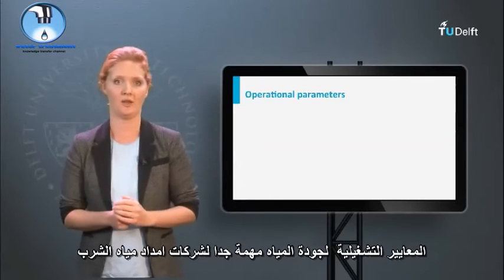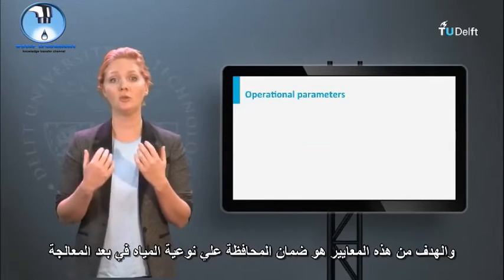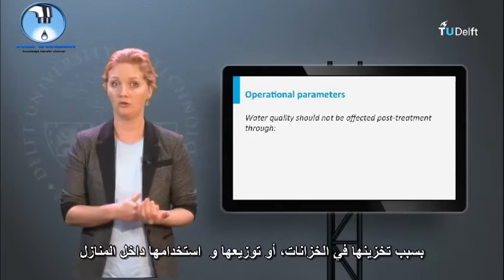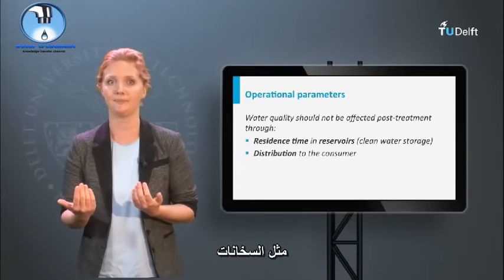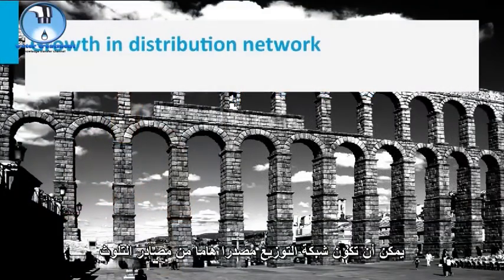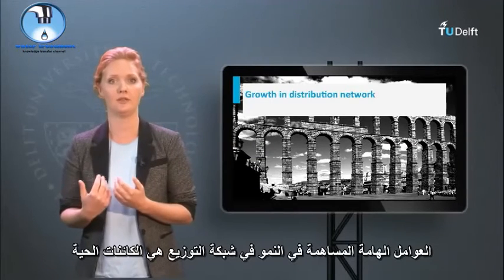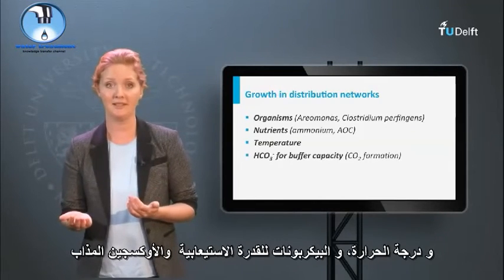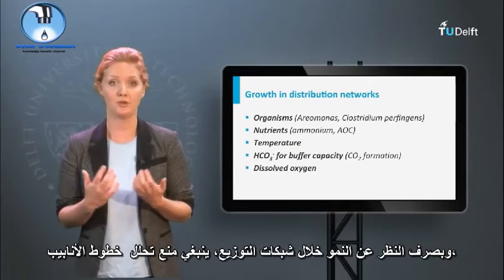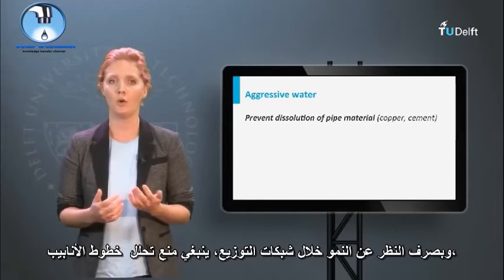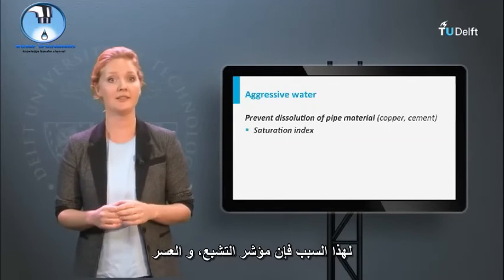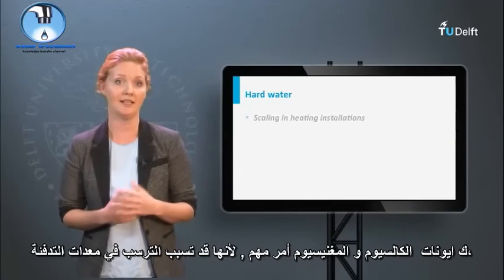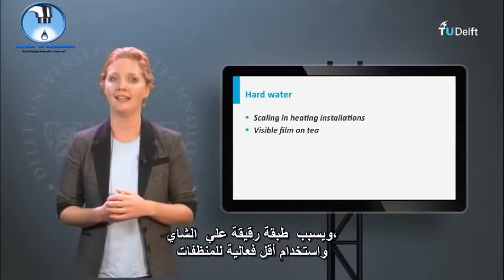Operational water quality parameters are very important for drinking water supply companies. The objective is to assure that water quality is maintained post-treatment — it should not change because of storage in reservoirs, distribution, or use within households such as heating. A distribution network can be an important source of contaminants as organisms may grow in it. Important parameters contributing to growth in distribution networks are the organisms themselves, but also nutrients, temperature, bicarbonate for buffer capacity, and dissolved oxygen. Apart from growth during distribution, dissolution of pipelines should also be prevented, so aggressive water must be avoided. For this reason, saturation index, hardness, and pH are important. The hardness of water as calcium and magnesium ions may cause scaling in heating installations, a film on tea, and less effective use of detergents.